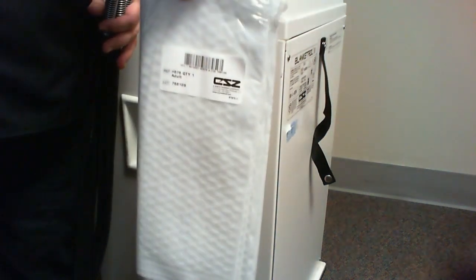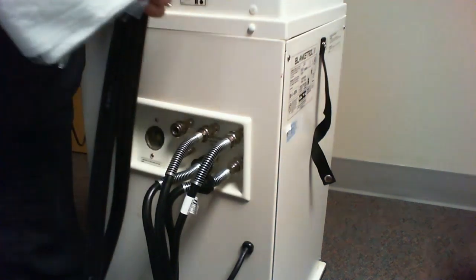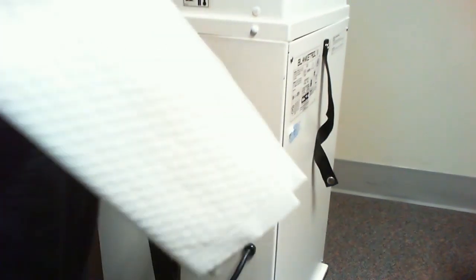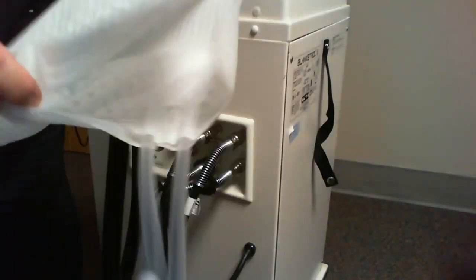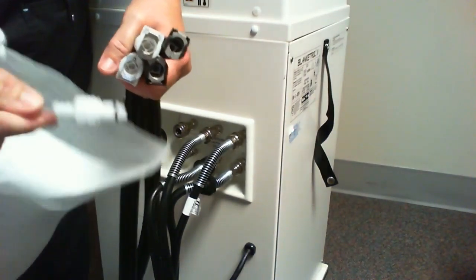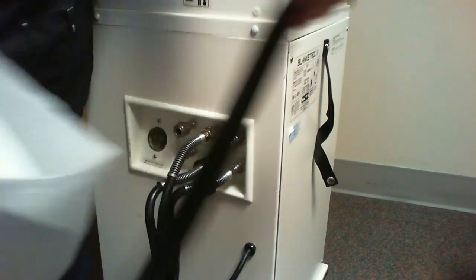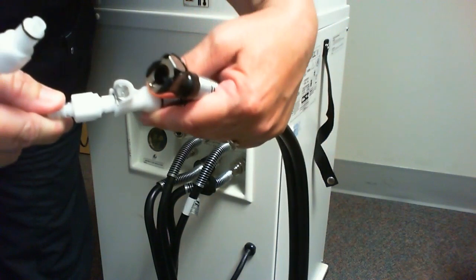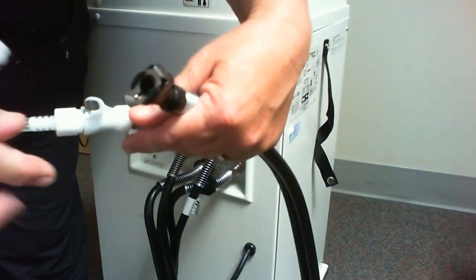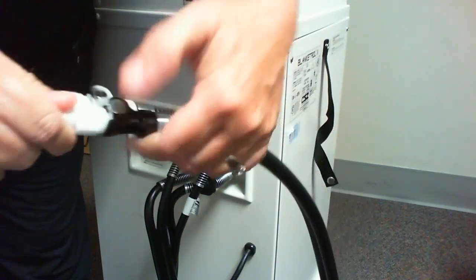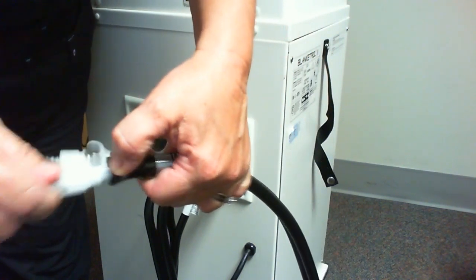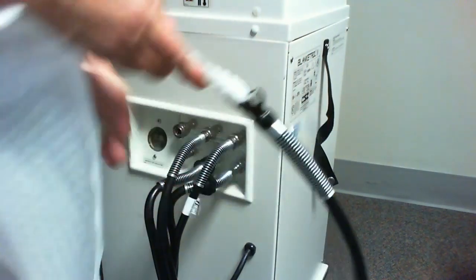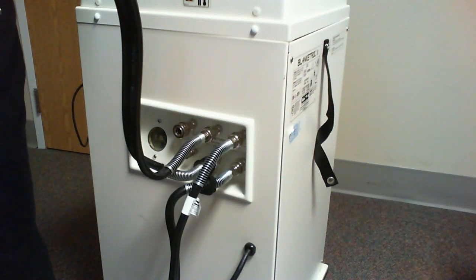Now I'm going to go get my disposable blanket, and I am going to connect. So here is my blanket. It's a nice, soft, conducting material. And I'm going to find the end that has the tubings. And so I'm going to take one of the cables, and I'm simply going to snap these. They friction fit, and you'll hear a click. Friction fit. To remove them, just push in on this metal part and they come apart. So friction fit. Now this blanket is ready to go. And I do the same for my other set of tubing.